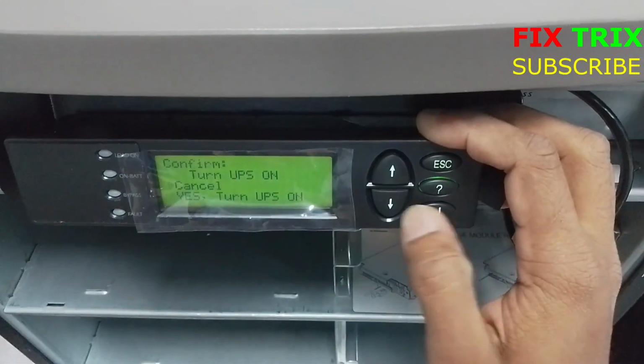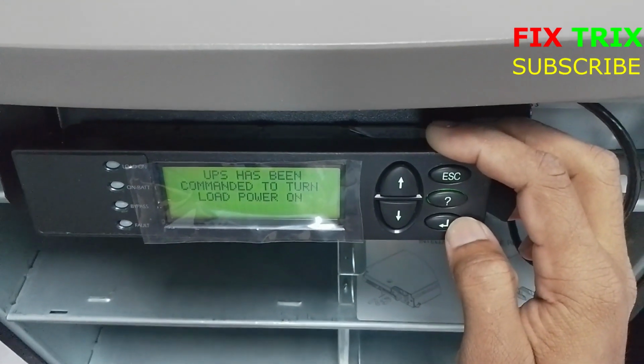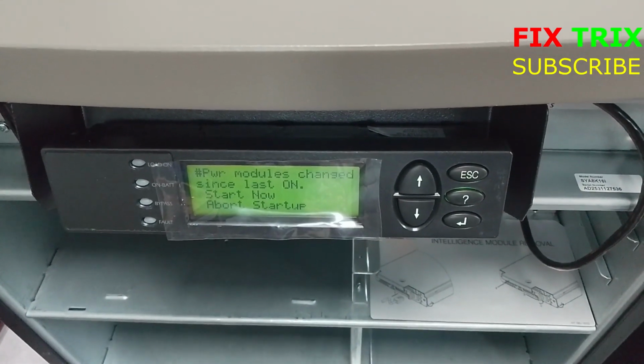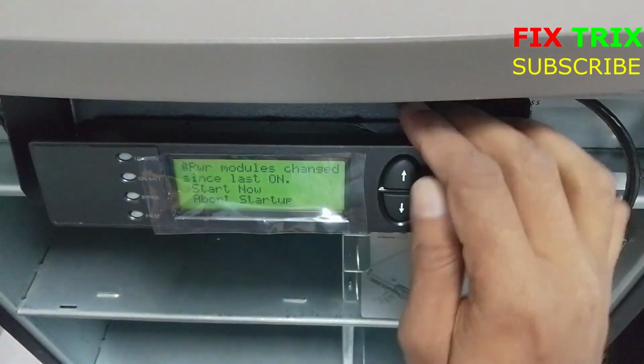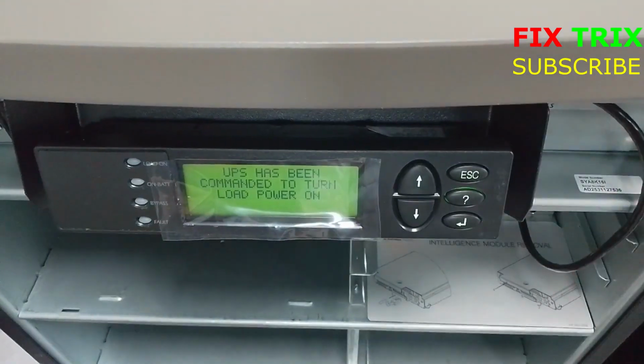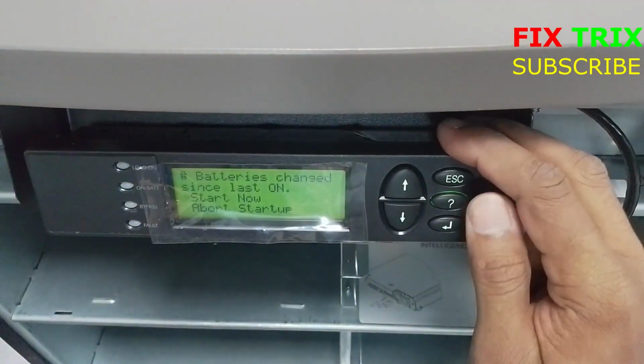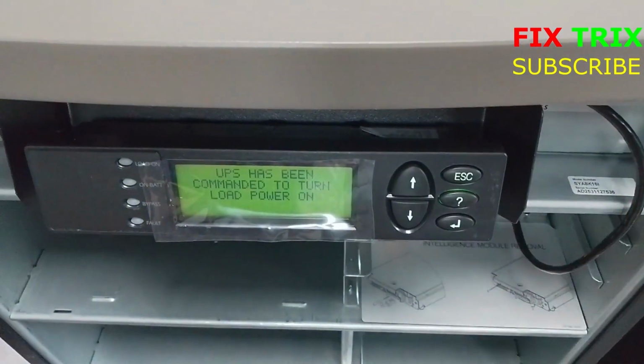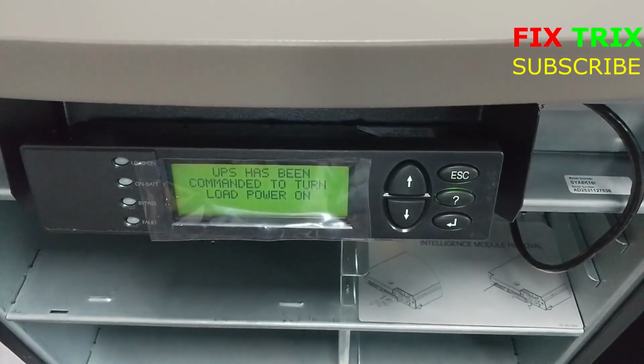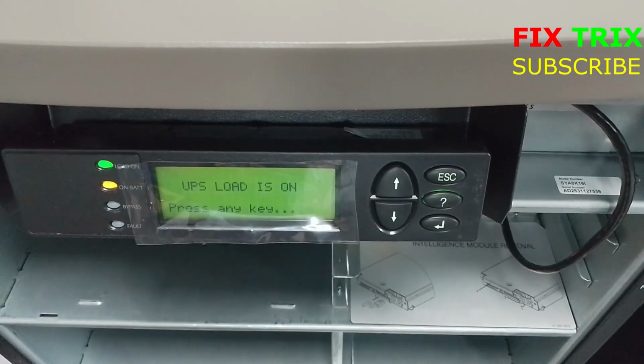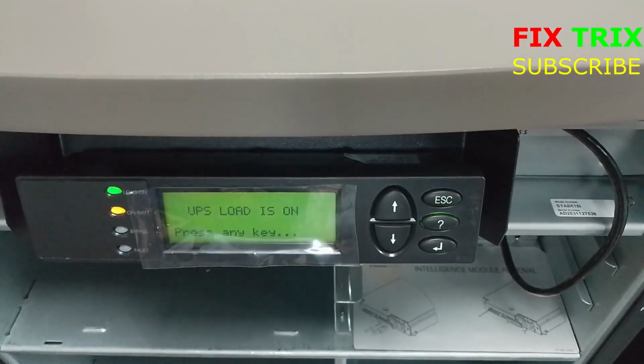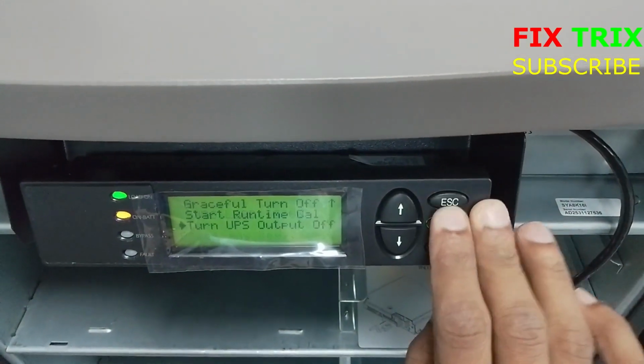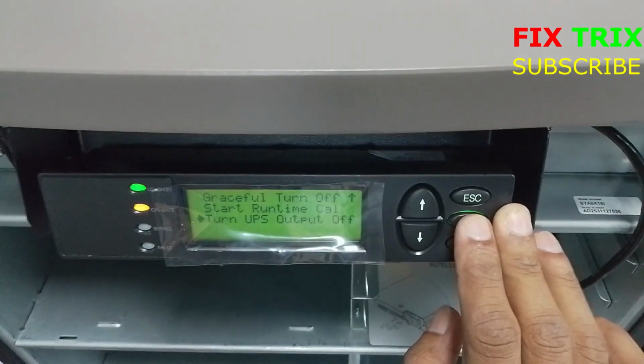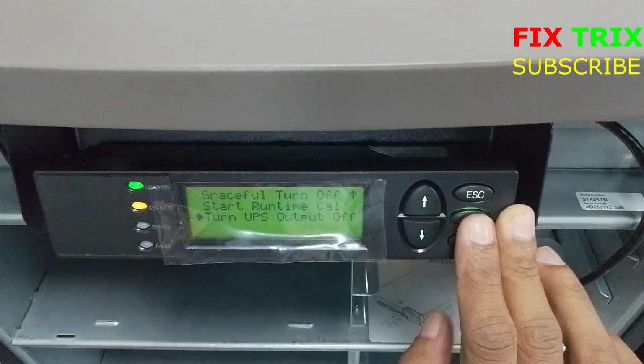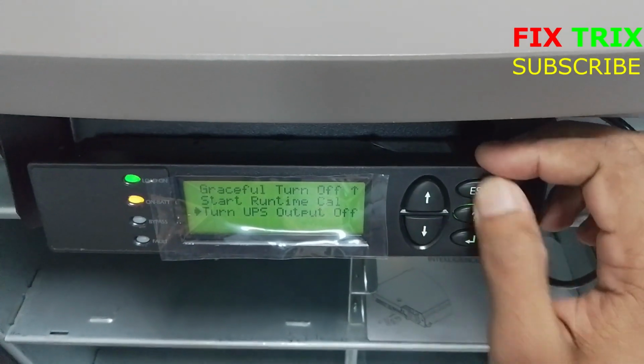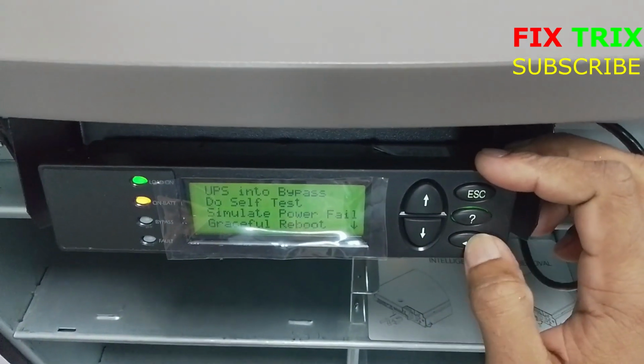Now that the load is on, we run the self-test again. This time the self-test starts and runs normally. We wait until the test is completed and confirm there are no alarm or errors. Now before installing all power modules and battery modules, we turn on the maintenance bypass switch. Why is this important? When maintenance bypass is on, the load is powered directly from utility. The UPS internal power modules are not supplying the load. This means the servers and equipment continue running safely while we work on the UPS.